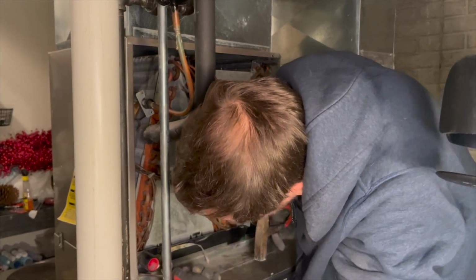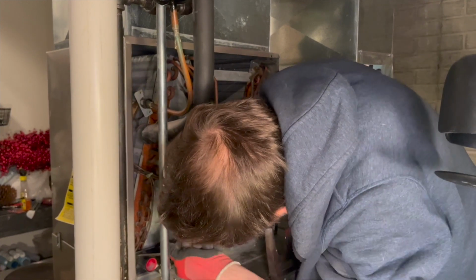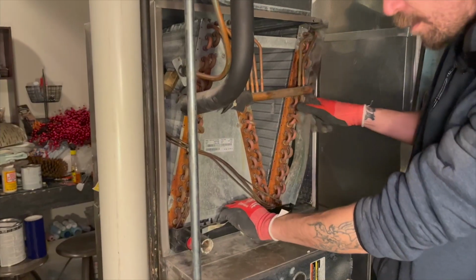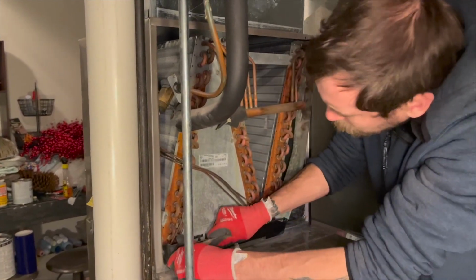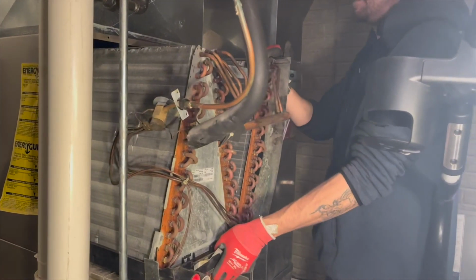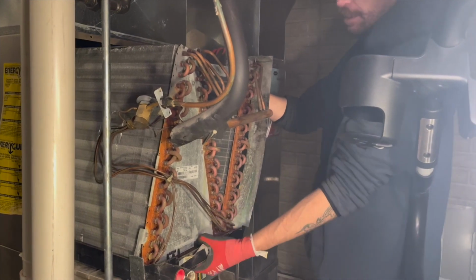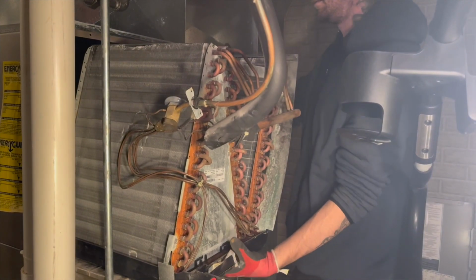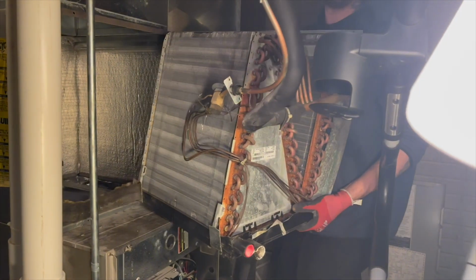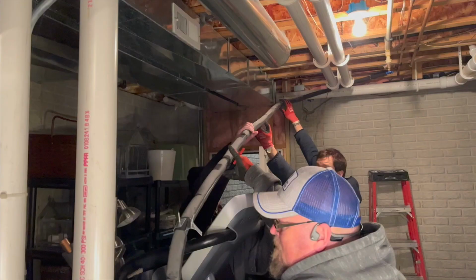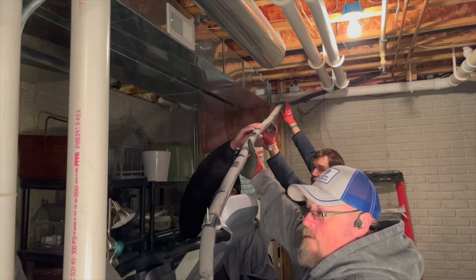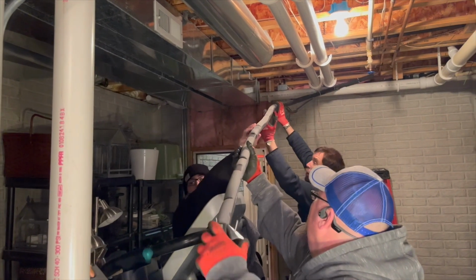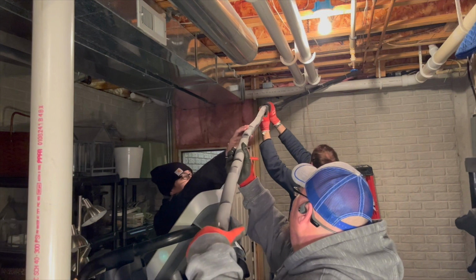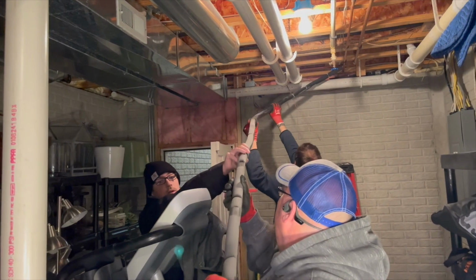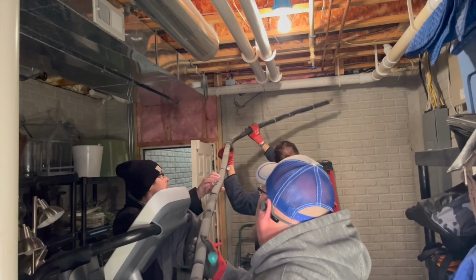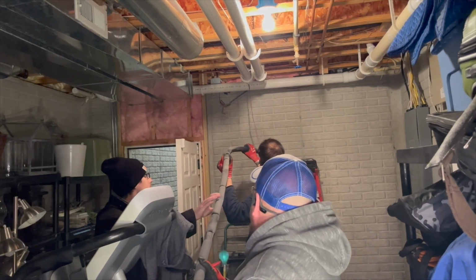Sometimes it's easier to remove a cased coil and replace the whole thing, but in this case, we elected to cut it out. So you can see the cover of the coil removed, and some gentle persuasion is required to extract the coil from the box. Eventually, we get the coil to slide out of the housing. Notice it's still attached to the refrigerant piping. In this next scene, we have eliminated the refrigerant piping. I would recommend that all new heat pump installations get new refrigerant piping unless the sizes match perfectly and the contractor can demonstrate a pressure test without leaks.